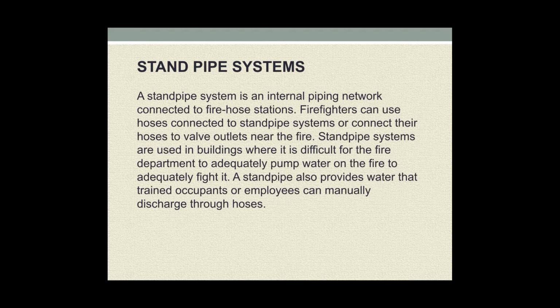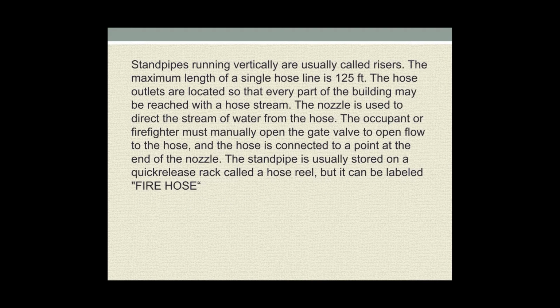Standpipe system. A standpipe system is an internal piping network connected to the fire hose stations. Firefighters can use hoses connected to standpipe systems or connect their hoses to valve outlets near the fire. Standpipe systems are used in buildings where it is difficult for the fire department to adequately pump water on the fire. A standpipe also provides water that trained occupants or employees can manually discharge through hoses.